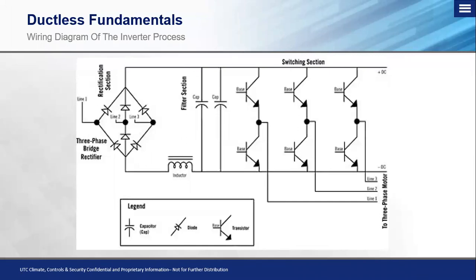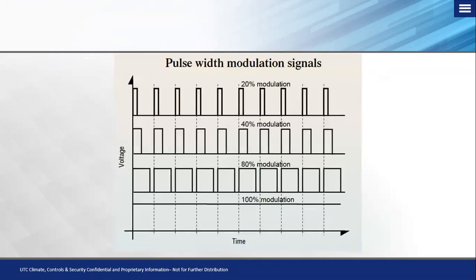However, when we are troubleshooting and taking our meter and going across the W, V, and U terminals, we are sending DC voltage, true DC voltage, to the compressor, but we're pulsing it to simulate the speed and to simulate an AC sine wave. So let's back that up. The compressor is an AC compressor. We are sending DC voltage to it.